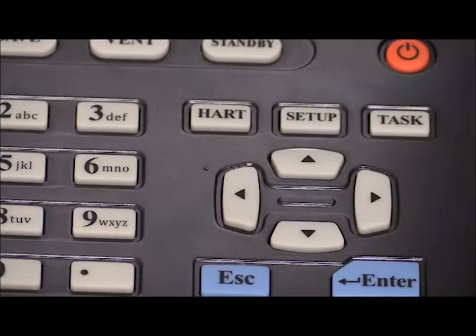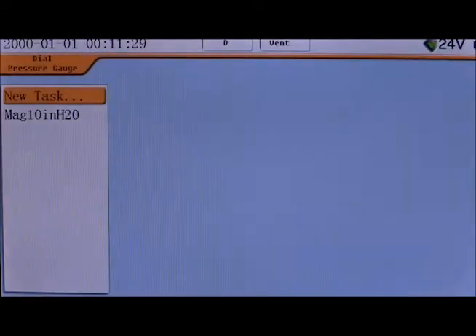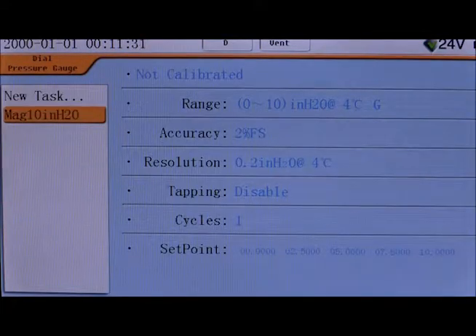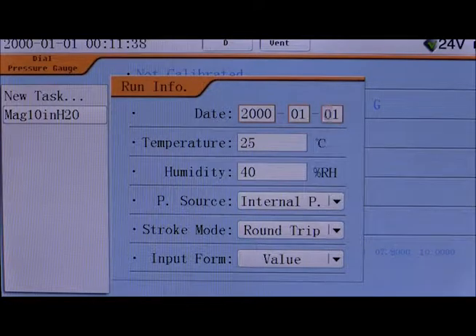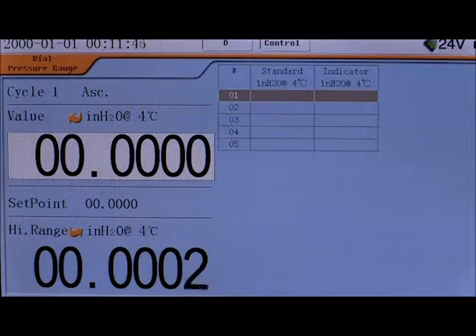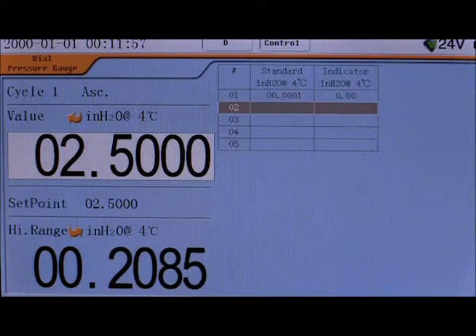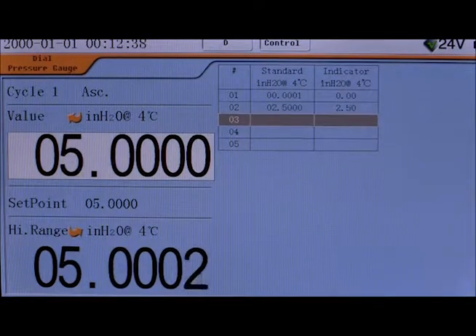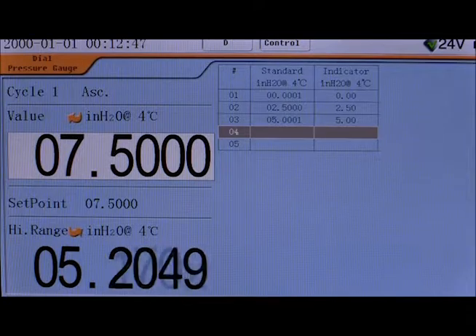With the 761, pre-programmed tasks can be set up and stored in the calibrator's memory. I've created a 5-point test with the specifics of this gauge and saved it as a task. I'll select the task and then select Run to start the test. After confirming the environmental conditions and how the test is to run, press Next and the test will begin. The test screen is set up to display the pressure of the 761, which turns green when the pressure set point is reached and is stable. The highlighted box is the reading of the DUT.